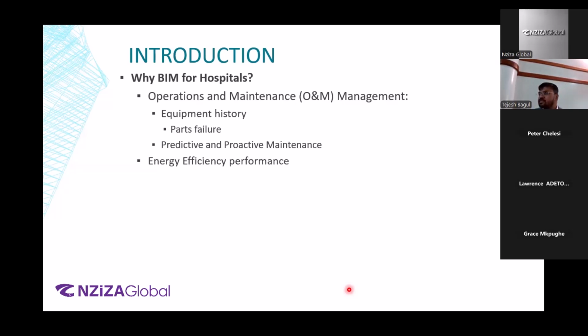Next is the energy efficiency performance. As I mentioned, we will talk about the energy component when we are doing the heat load calculations as well, right? So when we do heat load calculations, we have Q equals mCp delta T. Very common equation in the field of mechanical engineering, right? There is temperature T1 on the outside, T2 on the inside. We have a delta T, and then we are trying to maintain the heat loads based on that particular calculation. Now, what we have designed our systems for and how it is actually behaving in the field, we can compare it with the previous record, what the design engineer had done in the conceptual level design. That is also where BIM will come into the picture.